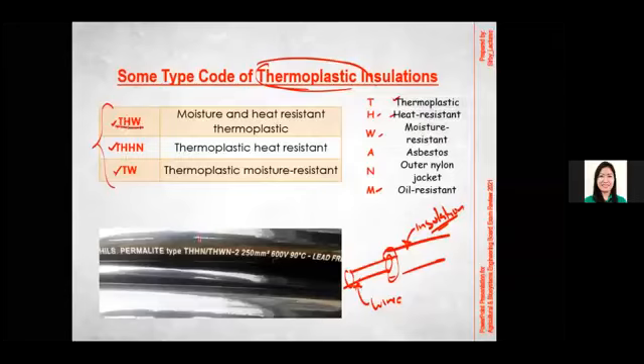So these are our cable markings. If it's THW, that simply means it's a moisture and heat resistant thermoplastic. THHN is a heat resistant thermoplastic, and TW is a moisture resistant thermoplastic. This depends on the applications or exposures - whether the environment where you want to expose this conductor has high moisture, or if it's going to be exposed to high temperature or something. So those are the applications of these different types. Also here we can see the markings, the voltages, and many other information.